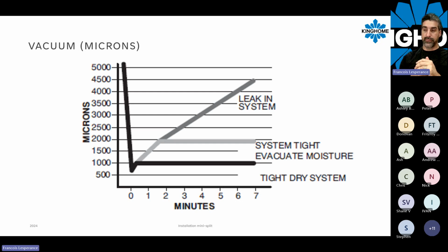If you bring the micron to 500 and then you stop the pump and the micron gauge number is stable, but between 1,000 and 2,000 microns, that's saying that you have a tight system, but you still have moisture, you still have humidity inside your line set. So maybe you will have to change the oil of your vacuum pump, because that's the oil that has the capacity to catch moisture. And so you will just continue your vacuum after that. And when you hit 500 and you're stable between 500 and 1,000, that means your system is tight and dry.